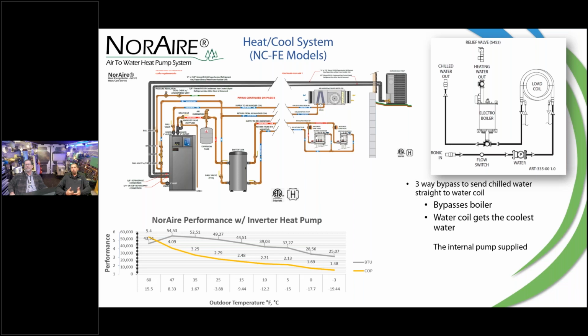You're going to find additions to this, I would say, are what, the more insulated. You're going to find it because now we're pumping some chilled water through that, through the coil. Anything and everything exposed can be subject to condensing, whether your valves, everything. There is a bypass though, so we're not putting chilled water through the actual boiler vessel.